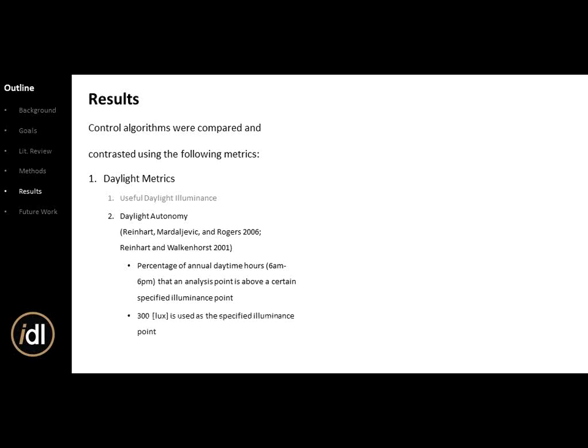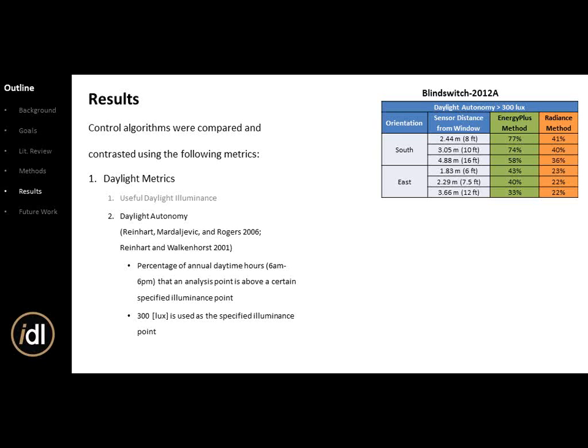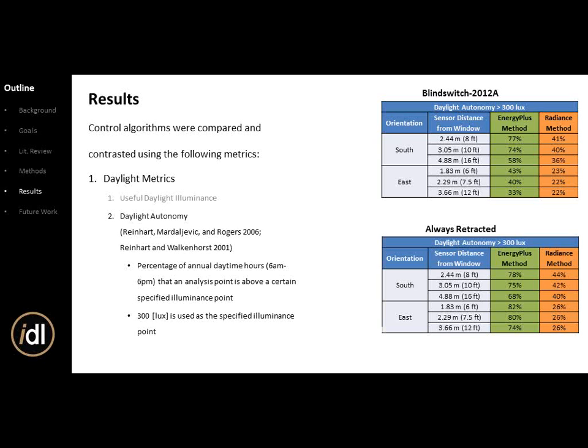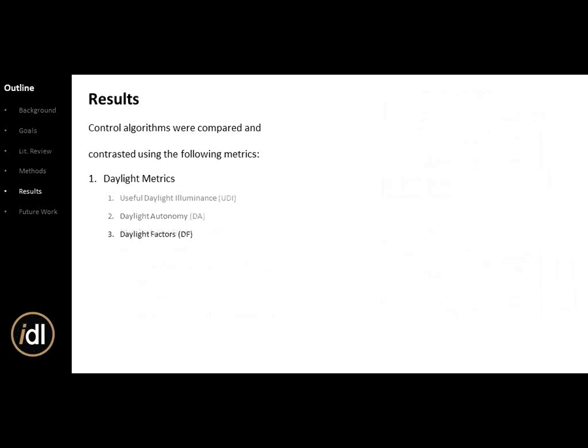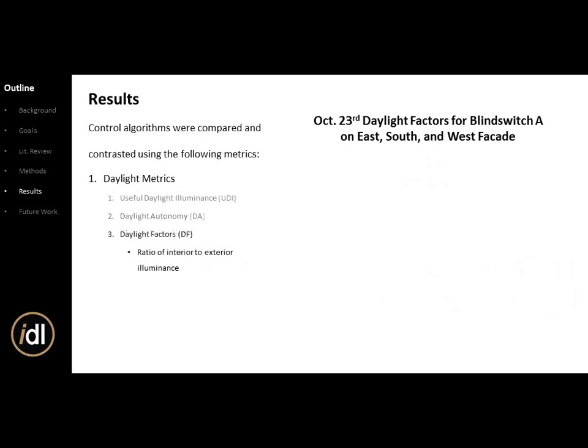Daylight autonomy is the annual percentage of daytime hours that a sensor point exceeds a certain illuminance value. We used 300 lux — about 30 foot-candles — which is standard for an office setting. Results for 2012-A and always retracted again show EnergyPlus significantly over-predicts interior illumination values compared to Radiance.